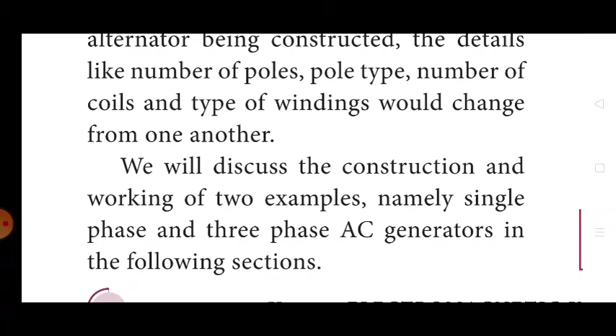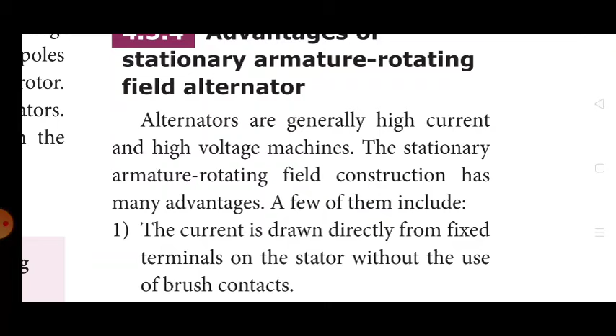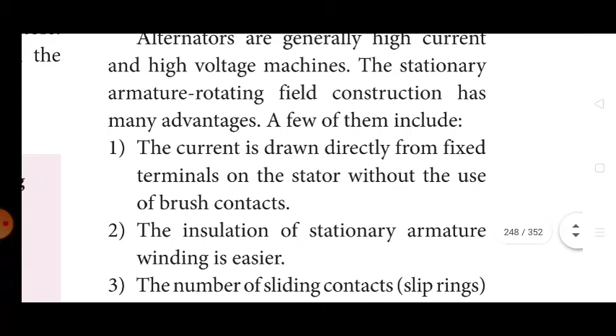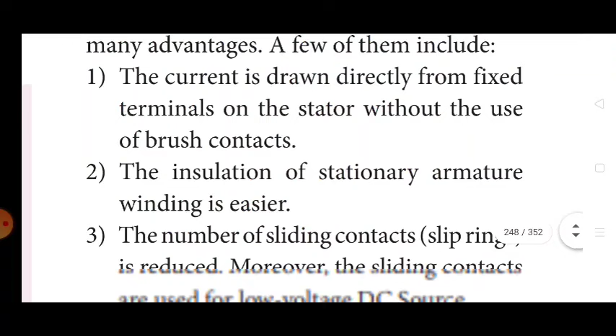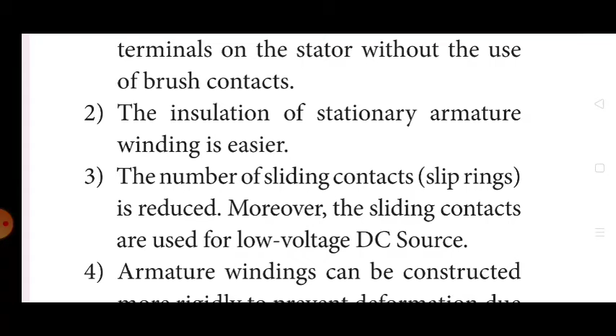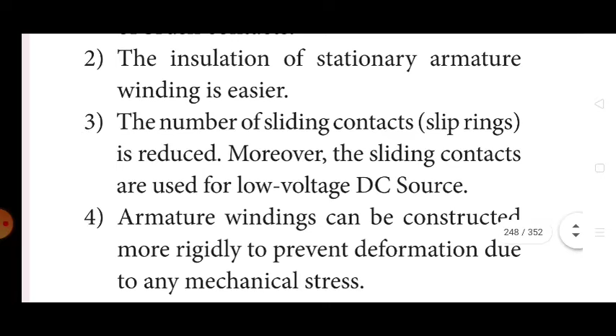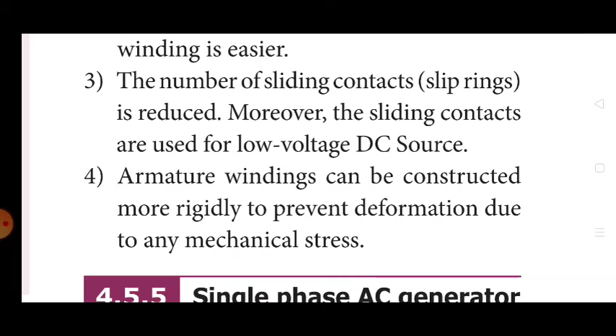Alternators are generally high current and high voltage machines. The stationary armature rotating field construction has many advantages. A few of them include: current is drawn directly from a fixed terminal on the stator without the use of brush contacts. Second, the insulation of a stationary armature winding is easier. Third, the number of sliding contacts, slip rings, is reduced. Moreover, the sliding contacts are used for a low voltage DC source. Armature windings can be constructed more rigidly to prevent deformation due to any mechanical stress.